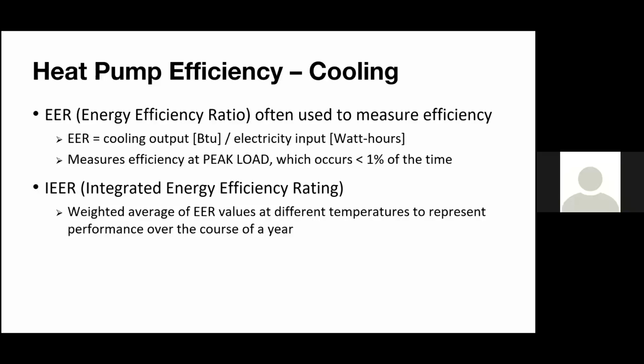So you'd have 100% loading, full demands, and we'd only be at that like 1 or 2% of the time, right? Then you have 75%, maybe at 60% of the time, and then 25% at 30% of the time, right? And you take all that data together, all those points together, and then you come up with a weighted average, an IEER number that is giving you a full representative of how efficient that's going to be and how that's going to perform over the course of that year, right?